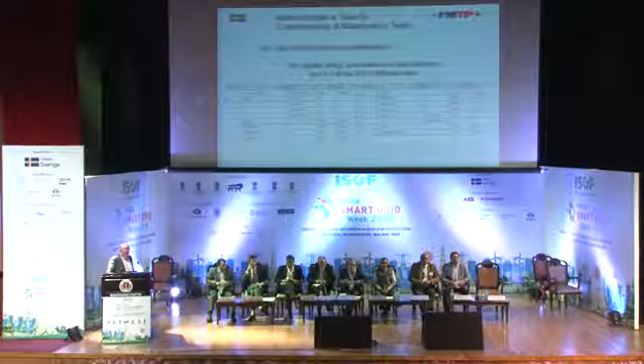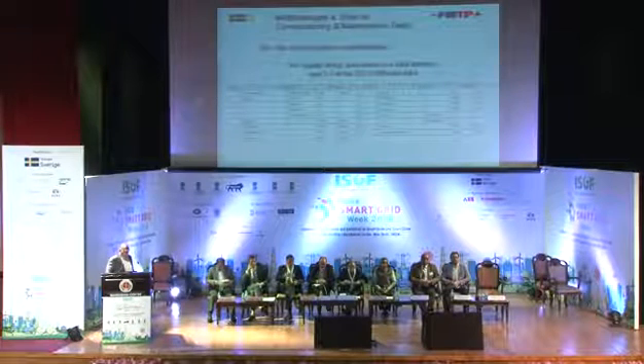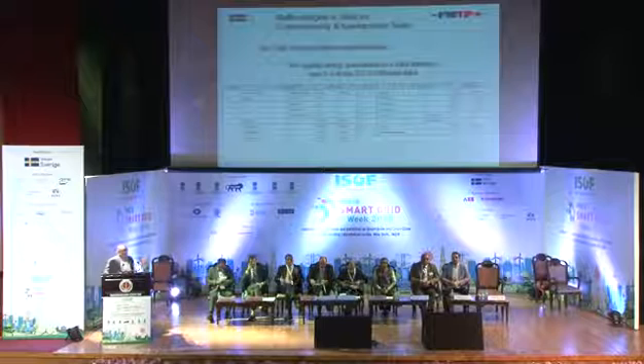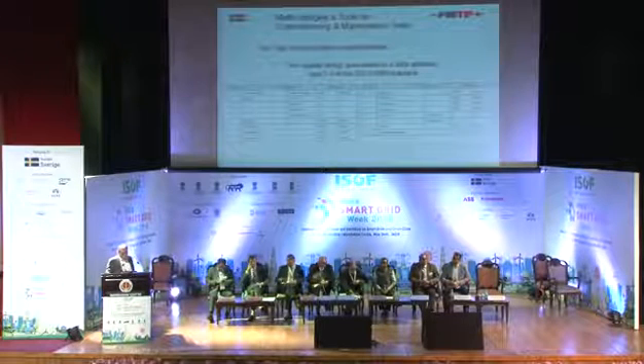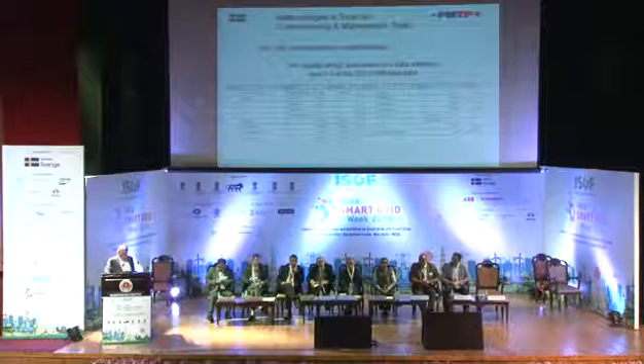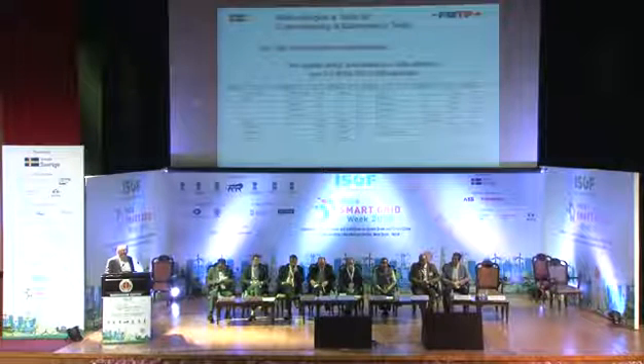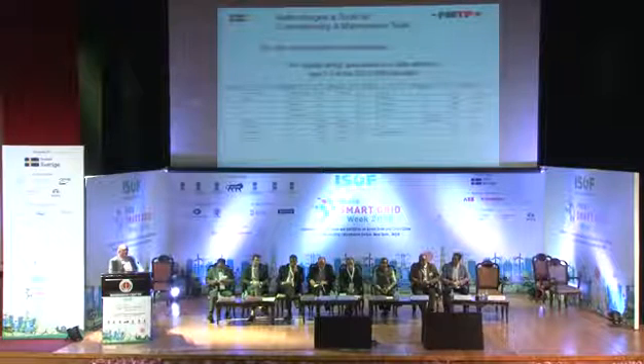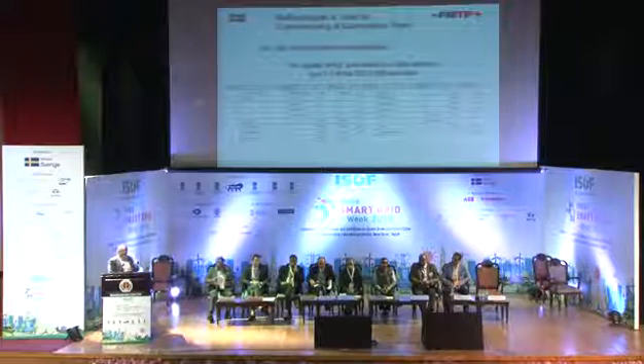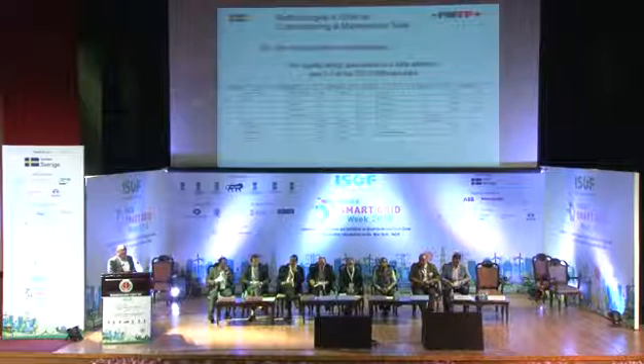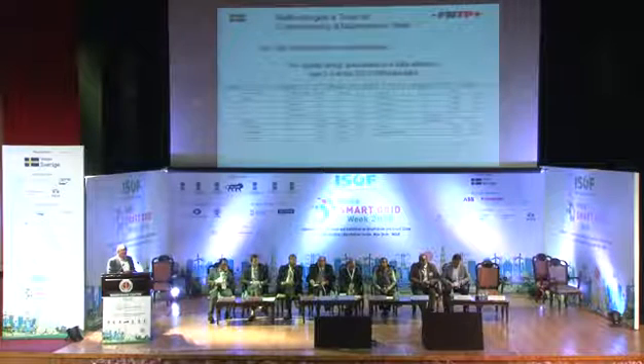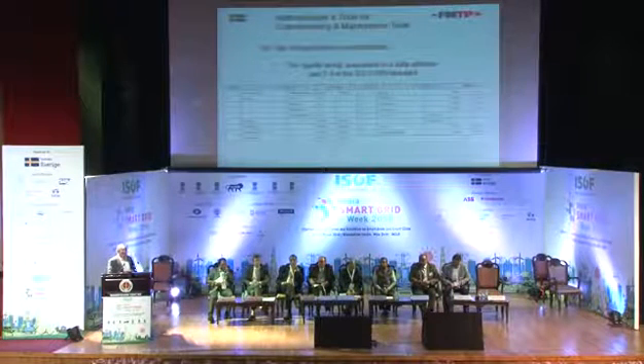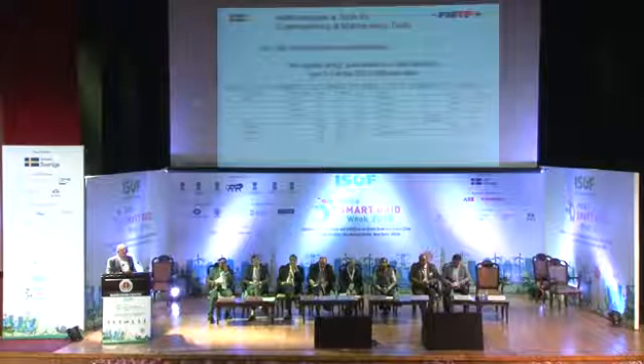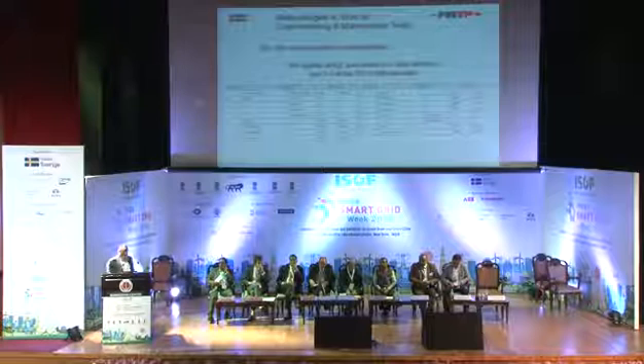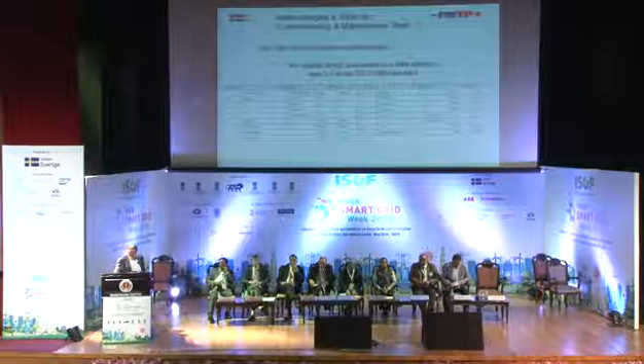These protocols have a quality string built in, so you have the message, the content of the message, and attached to that message you have the quality string. Very useful information that can indicate if there is a communication failure, a bad reference from the source, an inconsistency in the message, or if it's old data. So all this information is flagged into each of the messages that are broadcast, and this is very useful just to detect and troubleshoot.